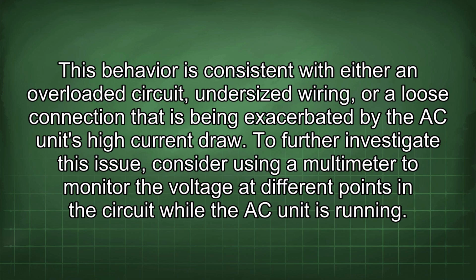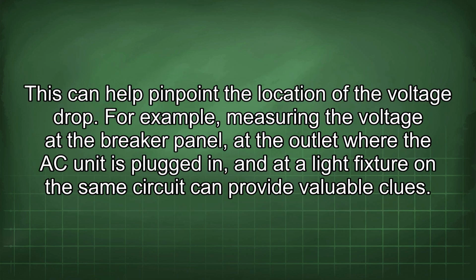To further investigate this issue, consider using a multimeter to monitor the voltage at different points in the circuit while the AC unit is running. This can help pinpoint the location of the voltage drop. For example, measuring the voltage at the breaker panel, at the outlet where the AC unit is plugged in, and at a light fixture on the same circuit can provide valuable clues.